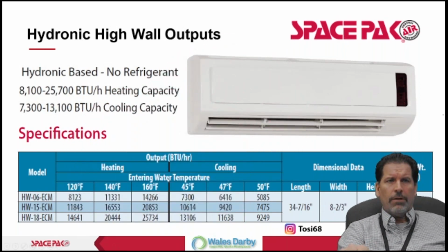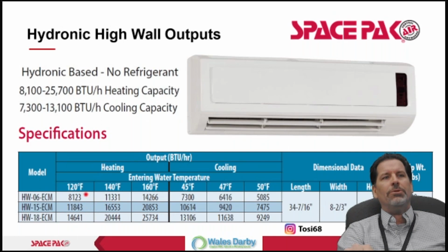All right, let's put my little laser on it. So entering water temperature, we need 4,000 BTUs. We can have a system delivered water temperature of 120, and we can pick between these 3 different models here.